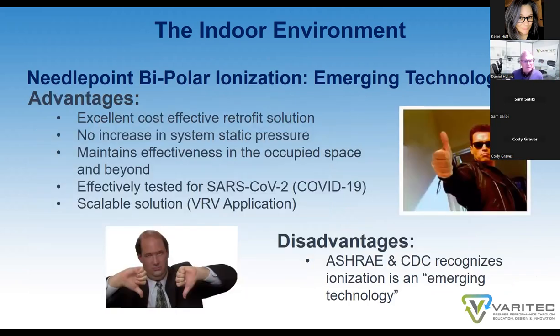So the advantages of needlepoint bipolar ionization are they're an excellent cost-effective retrofit solution. There's no increase in system static pressure. It maintains effectiveness in occupied spaces and beyond, effectively tested for SARS-CoV-2, and is a scalable solution. We can actually put an ion generator into a variable refrigerant air handler to inject ions most effectively into the space. The disadvantages are that ASHRAE and CDC recognize ionization as an emerging technology and do not give it their full support as they do other ventilation strategies ASHRAE outlines in the Epidemic Task Force.